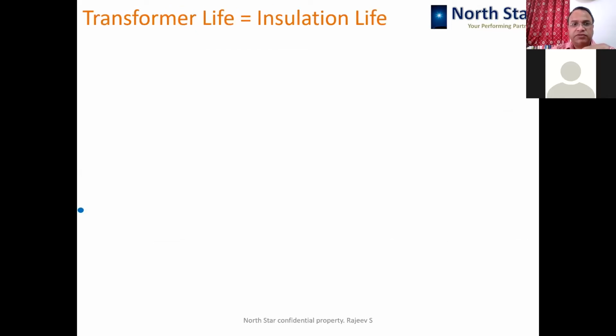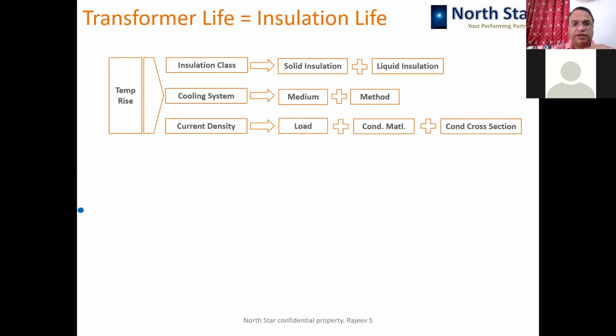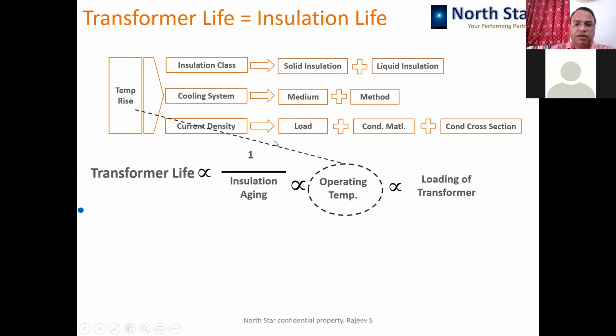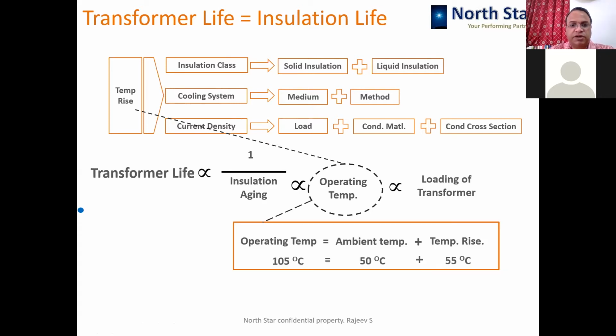So transformer life is nothing but insulation life, which we have understood in the past, because temperature rise corresponds to the operating temperature of the transformer, and the temperature rise depends upon three things: insulation class, cooling system, and current density. So the selection of all these three parameters will determine the maximum operating temperature or hotspot temperature possible for that transformer. The transformer life is inversely proportional to aging of the transformer, and aging is directly proportional to the loading and operating temperature. So the more the temperature, the more the load, the faster is the end of life approach of the transformer.